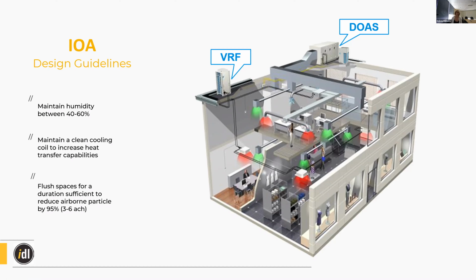And then the last one there, flush spaces for a duration sufficient to reduce airborne particles by 95%. So that's what we're going for, is really flushing the room by 95%. And that's when the 3 to 6 air changes per hour is the best guess at what it would take to flush a space. But obviously it's going to depend on the space.